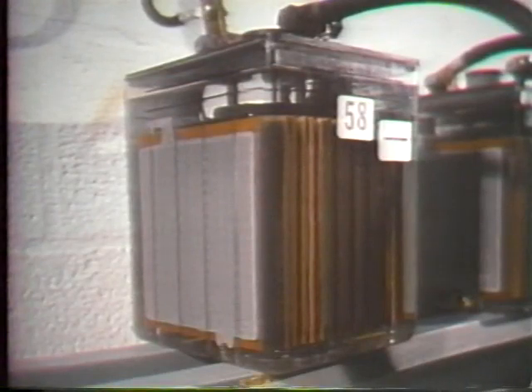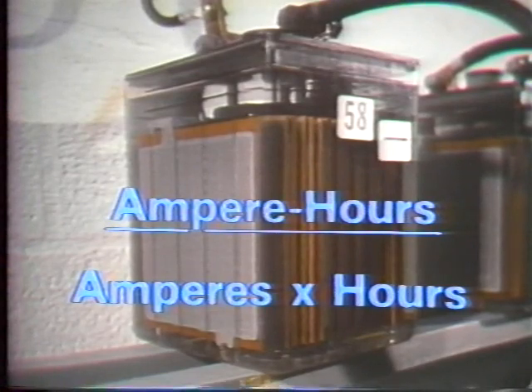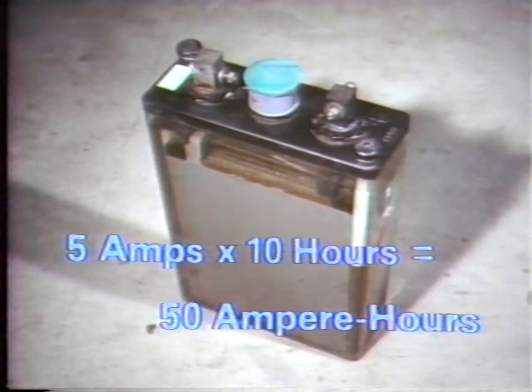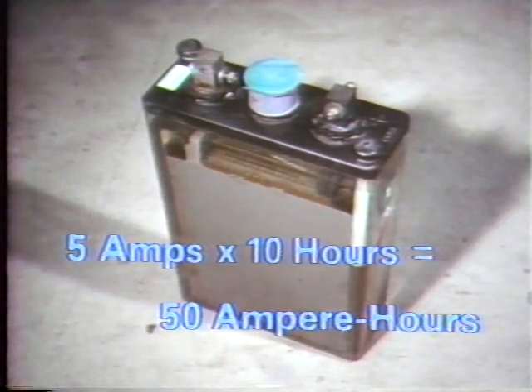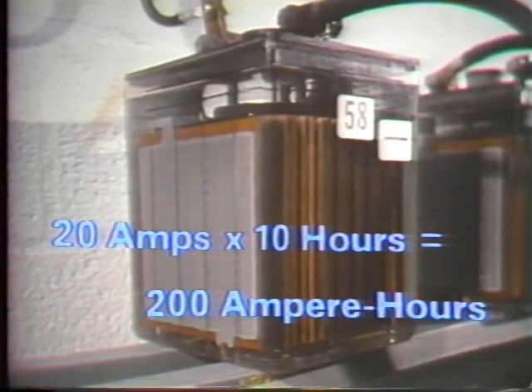The larger the plate area, the greater the ampere-hour capacity of the cell. The ampere-hour capacity rating of a cell is simply a discharge rate in amperes multiplied by the number of hours that the cell can deliver that current. For example, the smaller cell can deliver 5 amps for 10 hours, giving it a capacity rating of 50 ampere-hours. The larger cell can supply 20 amps over the same 10-hour period, so its capacity is 200 ampere-hours.